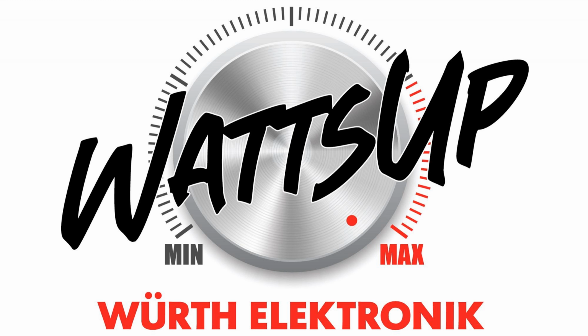So for instance, you would see that here, the software is opening a trace 2, a red color. I'm measuring the line with the peak detector, and I'm clear. Clear means that every second, because I set the dwell time at 1 second, it's measuring. It's an FFT receiver, so the measurement is really fast. In 1 second, I'm measuring from 150K to 30 mega.